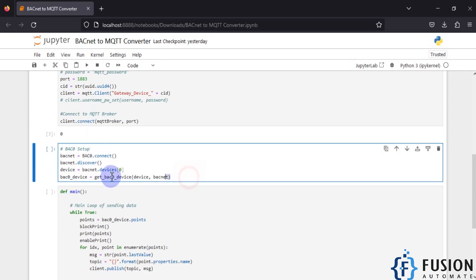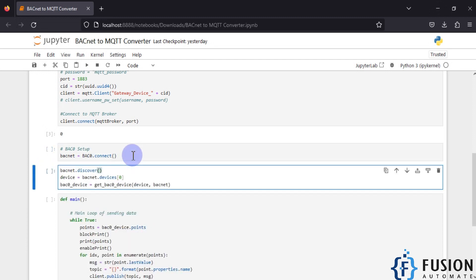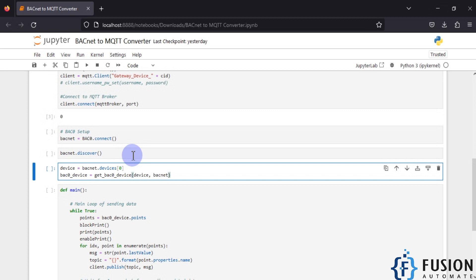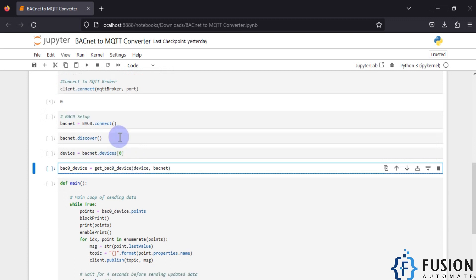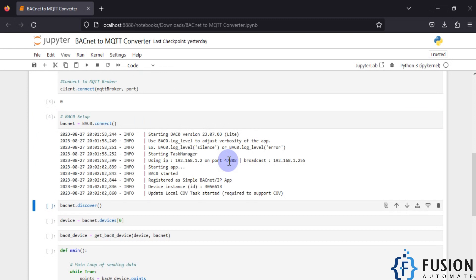Now we set up our BACnet device. I have used bacnet.devices[0] so it will connect to the very first device on my network. I only have the room simulator, so it will connect to that. It uses the IP and port number to broadcast a WHO-IS request to discover all devices available on the network.